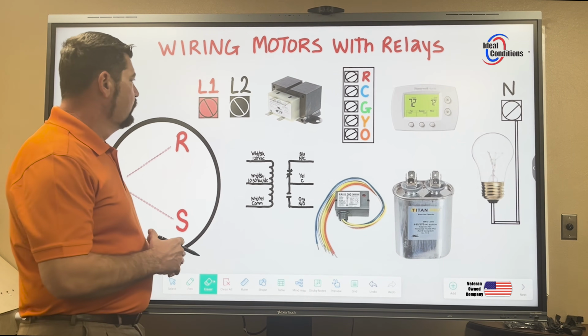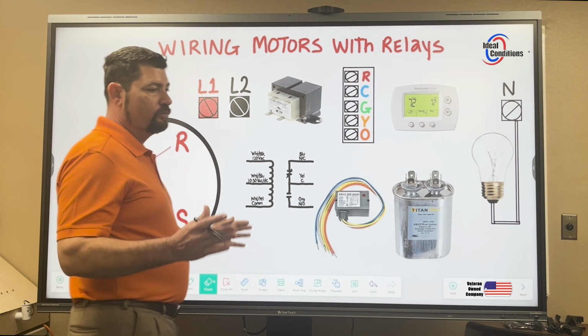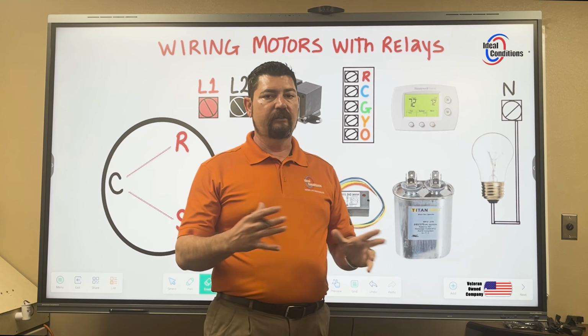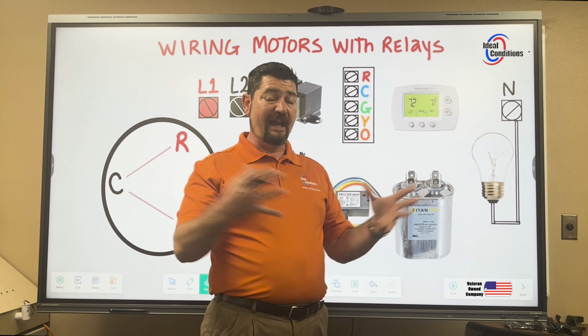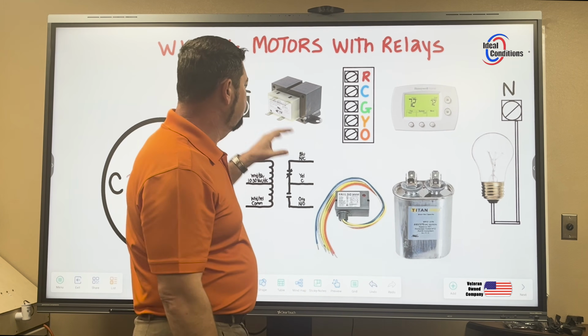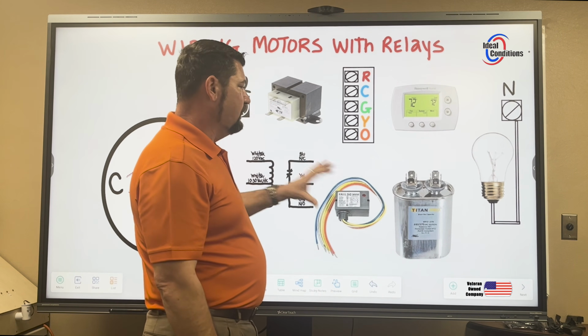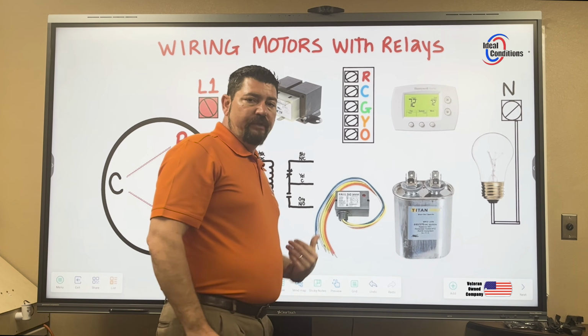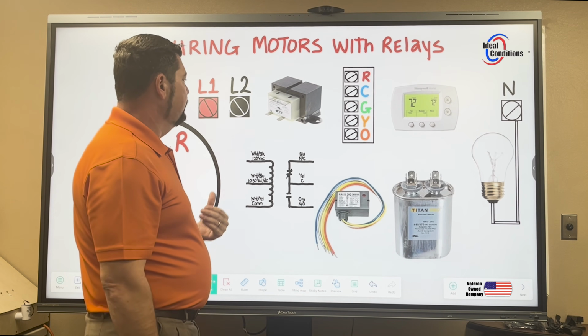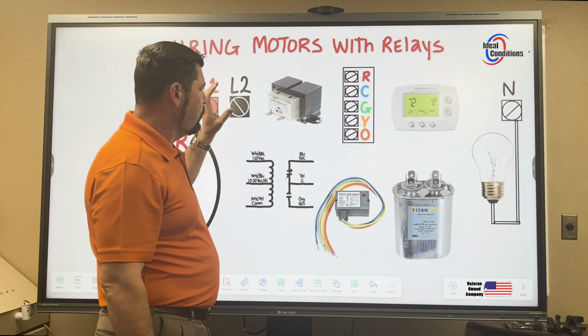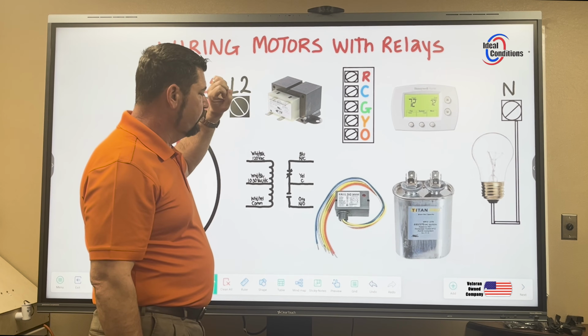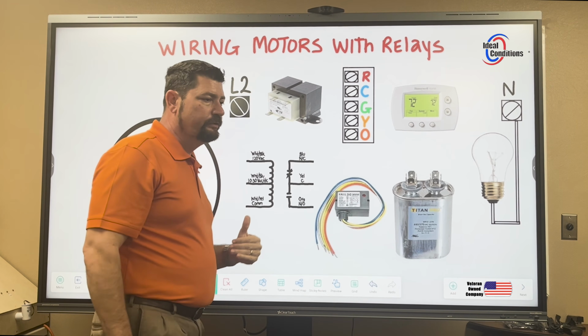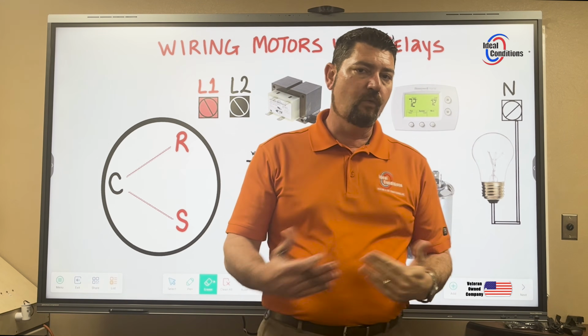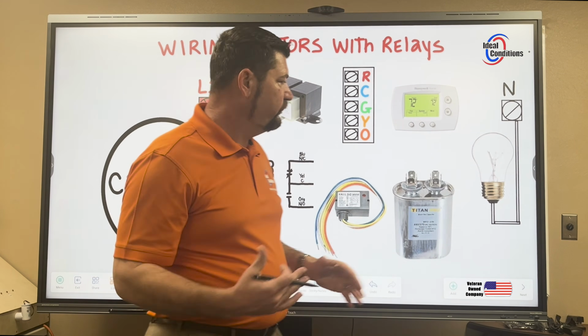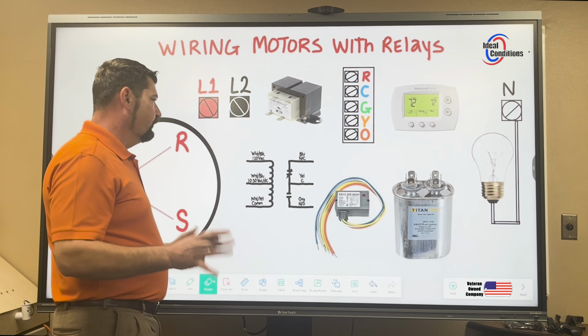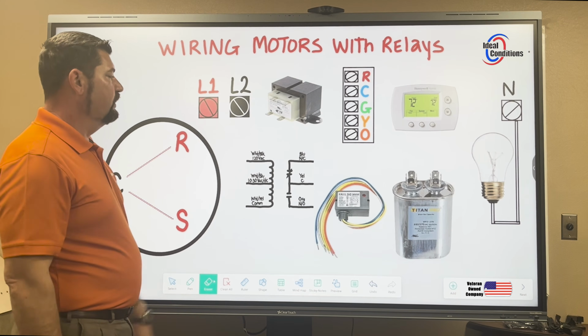At the end of it all, we want to make sure that we're not taking everything that's red or everything that's black and just hooking things up, high voltage and low voltage, at the same time. Some people won't wire up one component at a time. I don't think that's a safe thing to do, because you can easily start wiring up one component and forget that that red wire was high voltage and that other red wire was low voltage, and you don't want to cross those paths. Those paths need to stay separated for your safety and the well-being of the equipment.